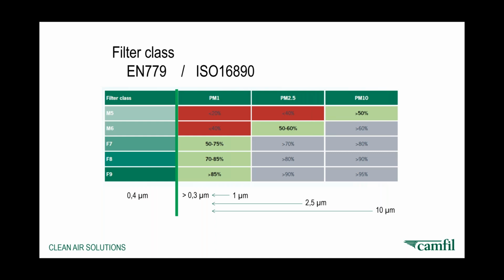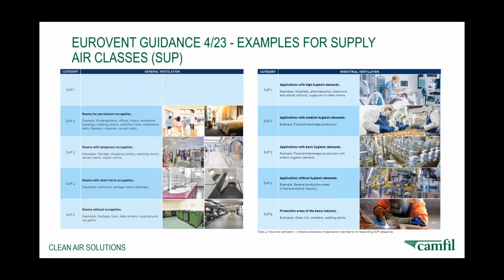And then when we look at the second standard that was developed in order to support facility management or building management activities, that's Eurovent Guidance 423. This standard helps you select air filters based on two main criteria: the supply air class and the ODA, or outdoor air, and the area that you're in. And you can see that they're for general ventilation or industrial ventilation.